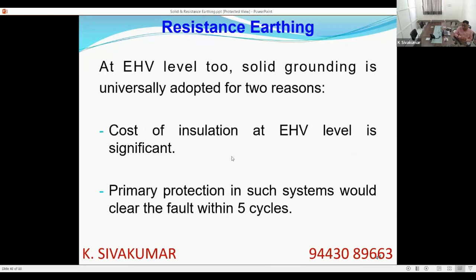Why? Because the cost of insulation is very significant as you go higher up in voltage, because the phase voltage also increases. Suppose you take a 66 kV system, the phase insulation is 66 by root 3, somewhere around let us say 38 kV, whereas the line insulation is 66 kV. So if you solidly ground, you can design your system, lightning arrestor, PT, everything for 66 kV by root 3 only. If you go for a non-effectively earthed system or impedance earthed system, you must design everything for full line voltage. So the cost difference between 66 kV earthing and 38 kV earthing is very huge.